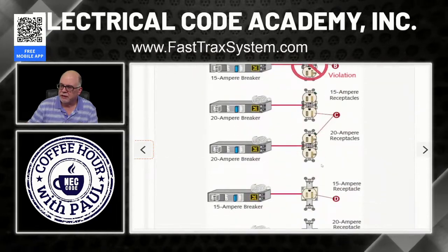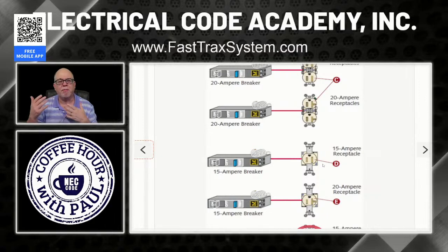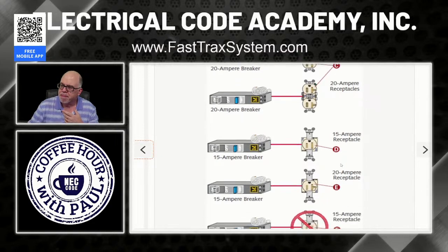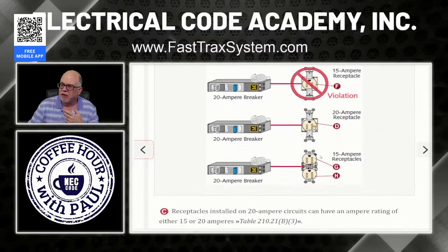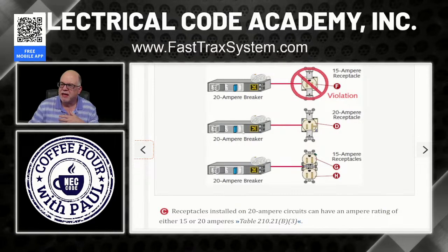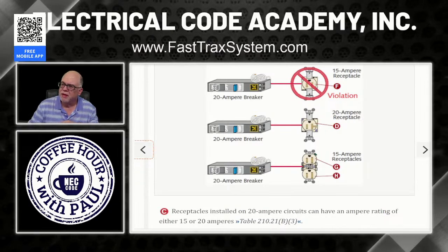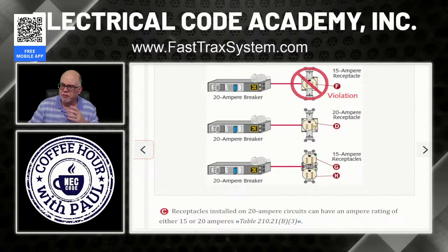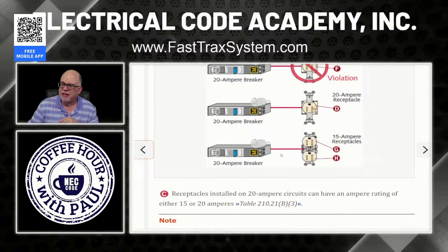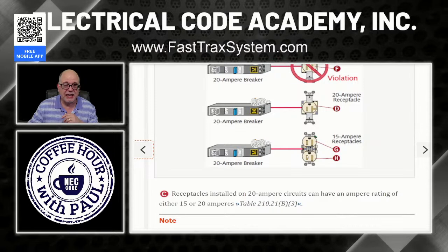All right, let's go on down here. Y'all doing great, and we're making great progress, and hopefully these are starting to now make more sense to people. All right, let's go on here. So here's a 20 amp rated overcurrent protective device. It happens in this case to be probably either a GFCI or an AFCI. Could be dual function, does both. And you see it's a 20 and a 20 single is perfectly acceptable, right? And then down here, again, like we saw before, a 20 ampere rated overcurrent protective device and a 15 amp rated receptacle. Again, that's perfectly okay.